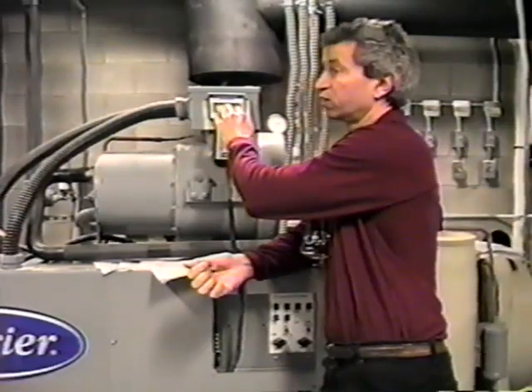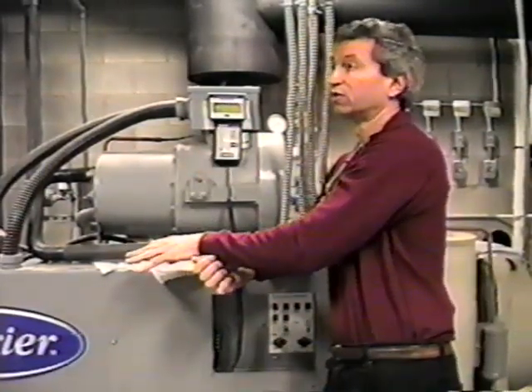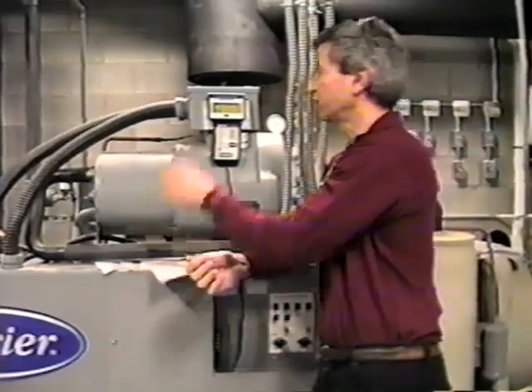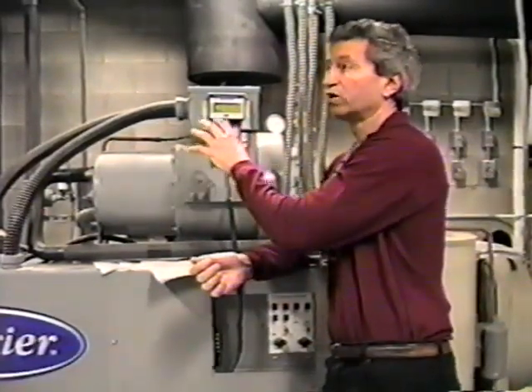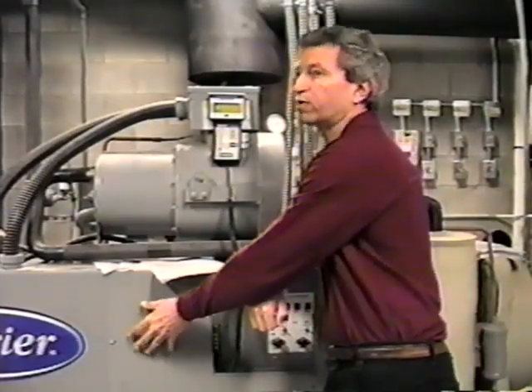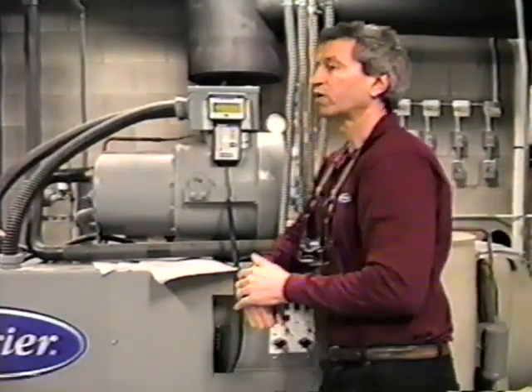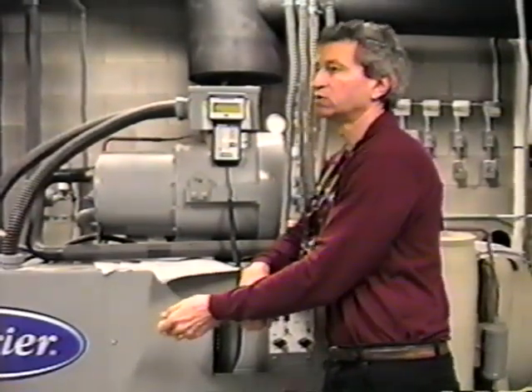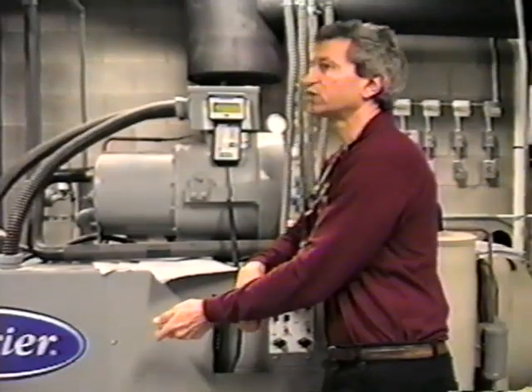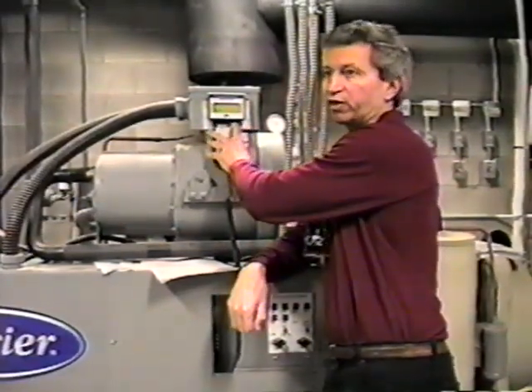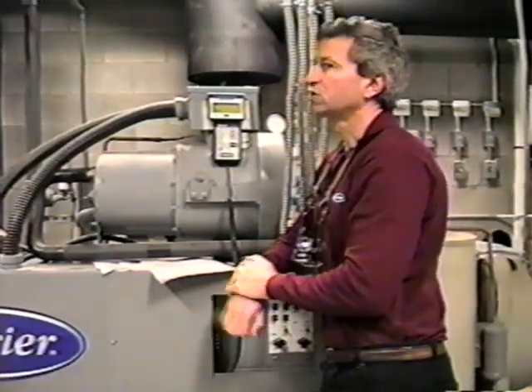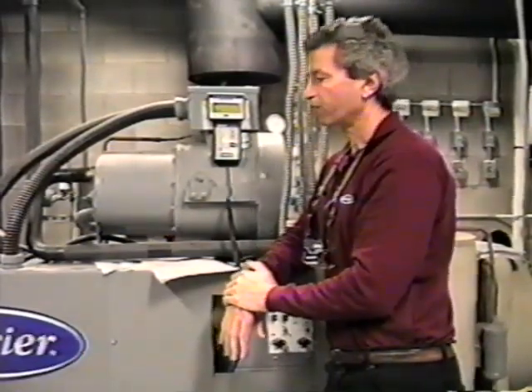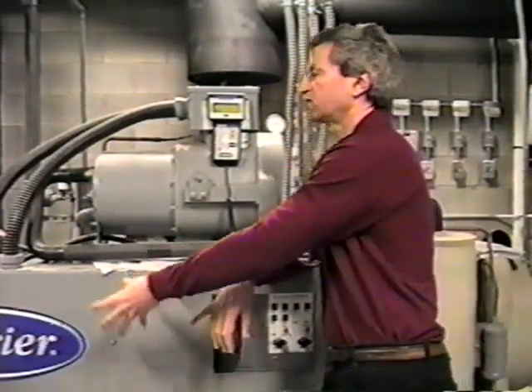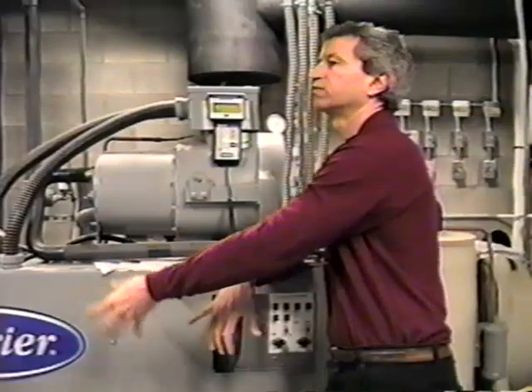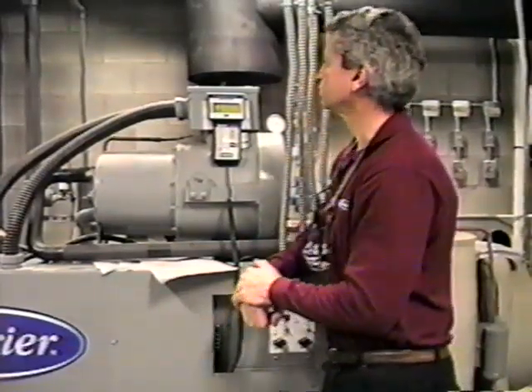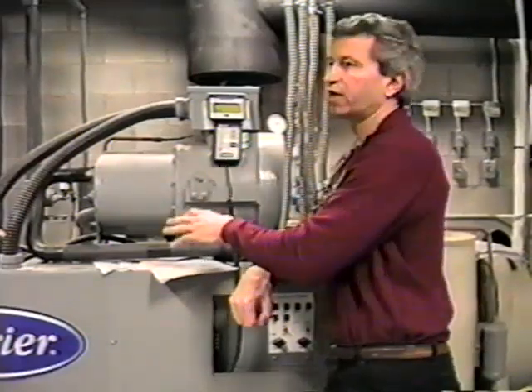So what you're going to get here is it's going to tell you that you have a compressor protection alarm. It's not going to tell you which one. Then you hit expand, and it'll tell you which one. But the reset of that is on a button on the compressor protection module board. So it has to be reset on that board independently. And then once that's reset, you can reset it by the usual means here. So that's a little bit confusing, but because that's kind of its own separate brain, it has to be reset independently. And again, it's going to tell you that in the manual.